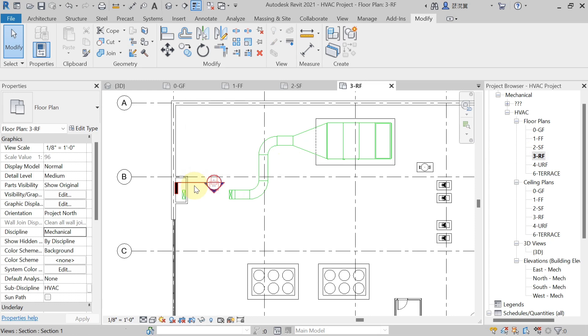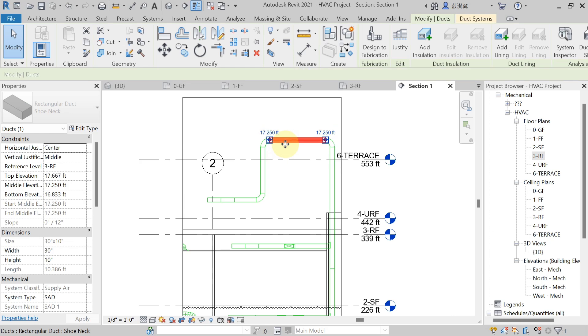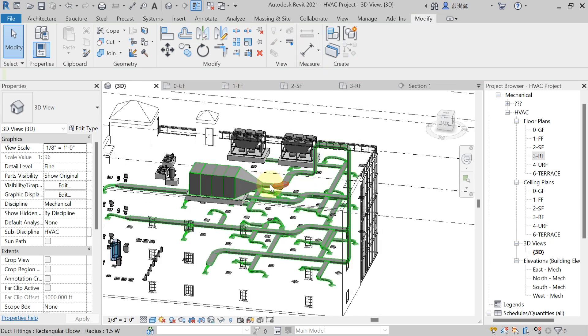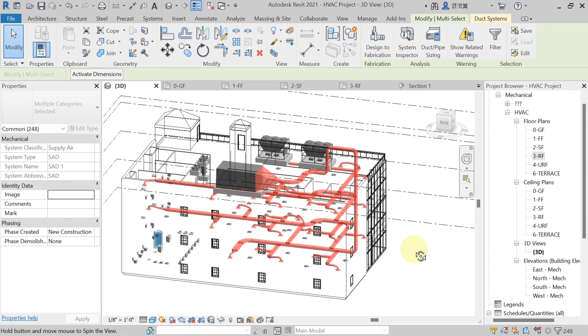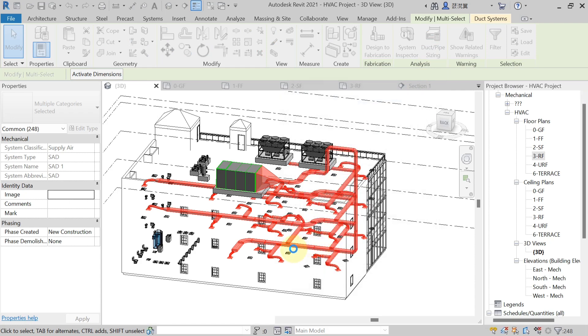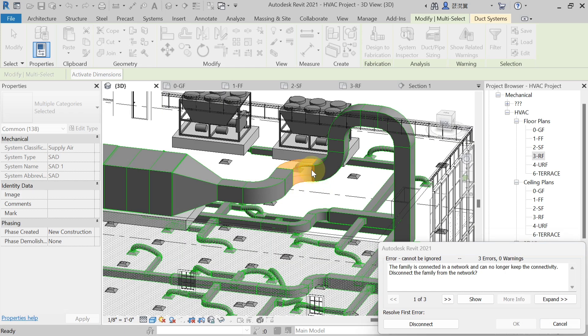In the section view on the roof floor, take the duct up a little bit. Then come back to the 3D view, take the cursor near any duct, press Tab twice, and left-click to select the complete ducting layout. Hit Duct or Pipe Sizing, choose the Equal Friction method, and click OK. Wait a moment for the automatic duct sizing to generate — but the same fitting problem may appear again.